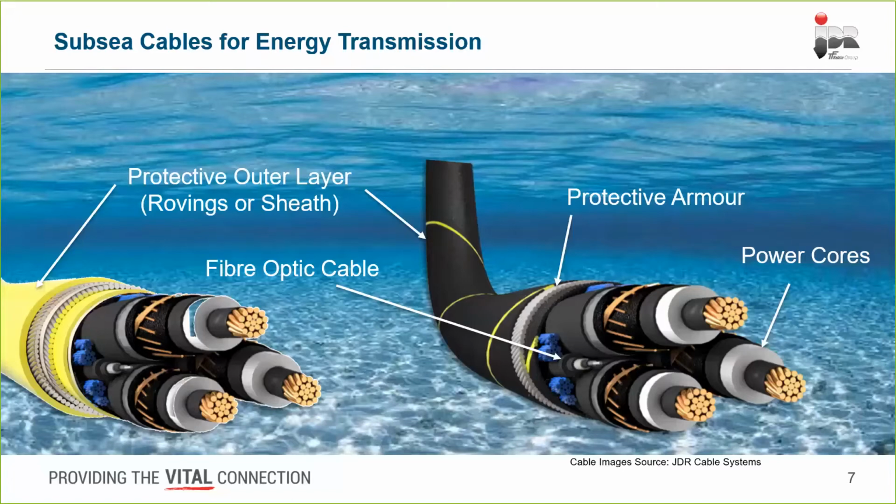However, if you're in a scenario where you have a turbine with a cable entrance point that's a lot higher up, then you'll have a hanging length of cable down to the sea floor, and that hanging length is subjected to current and wave loading, which means that it will move quite a lot. We will need to build in a more robust cable so that it can withstand that kind of fatigue motion, as well as providing us that energy. And that's why for dynamic cables you'll see a bit more armor, and it's contrahelically laid to give it more torsional balance, and you'll have protective sheaths, so more abrasion protection as offered by these sheaths as well.